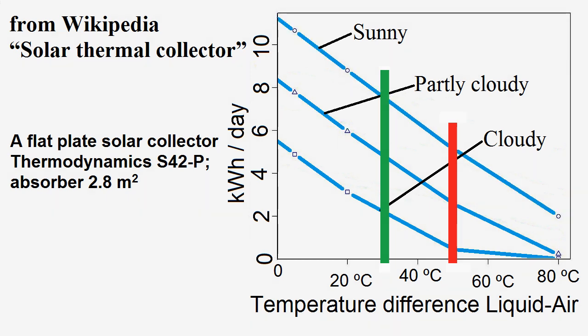So, we should try to reduce the temperature of the liquid inside our solar collector as much as possible, and usually we can find some traditional and non-traditional opportunities to achieve this. For example, sometimes we can refuse antifreeze inside collector pipes, or we can increase the performance of the heat exchanger which transfers heat from the antifreeze to water of our heat storage. Very often, we can achieve a noticeable decrease in the temperature of the collector liquid if we increase the volume of our heat storage.